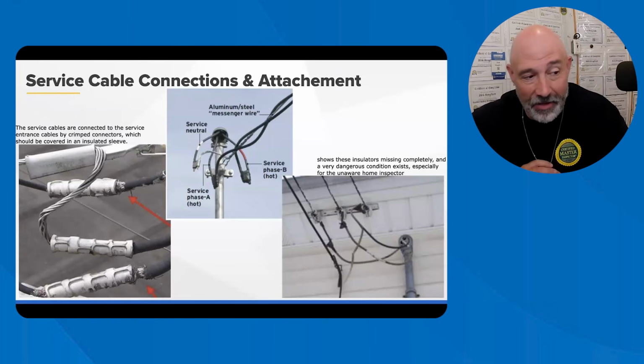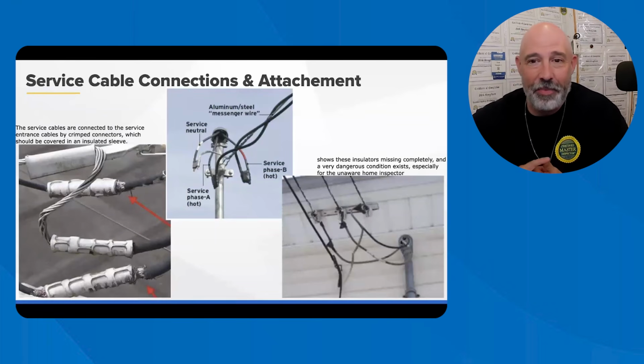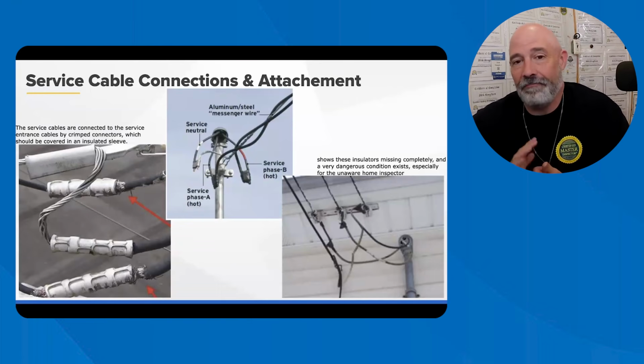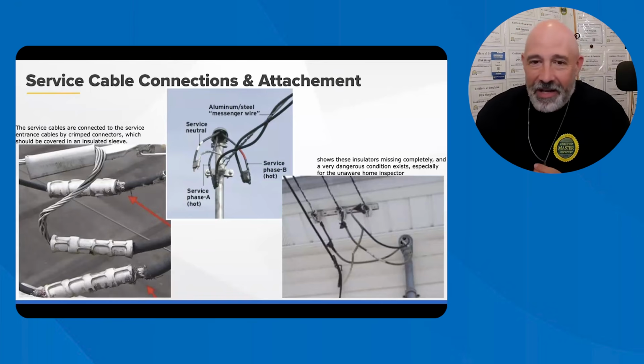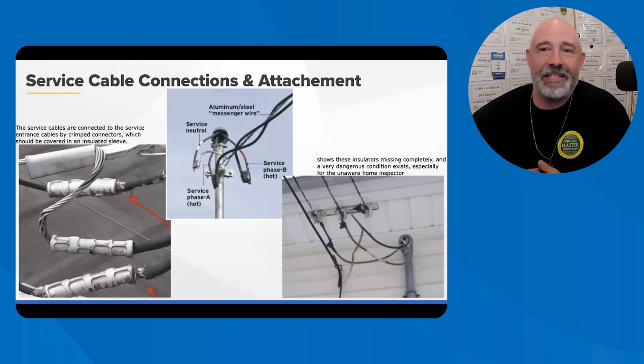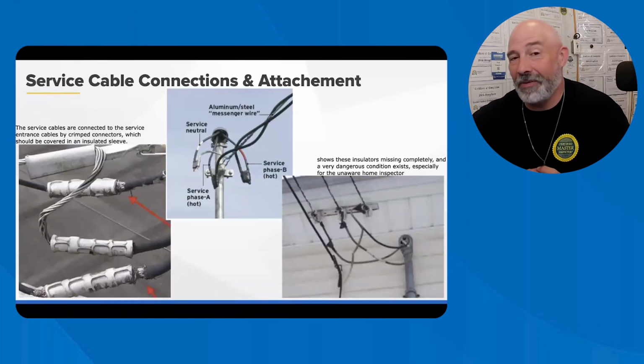Oh, yeah, definitely call it out. Make sure further evaluation from an electrician right there, right away. Inspector should verify that the point of entrance or the attachment, and the service conductors, are properly supported. I still can't get over that picture. And the service drop maintains at least 10 feet of clearance above grade. So no little kids are gonna sit there and play with it.